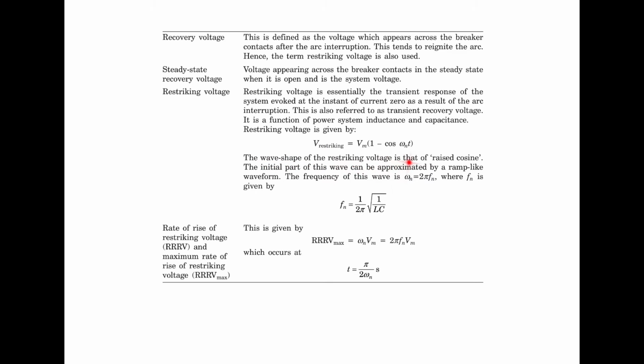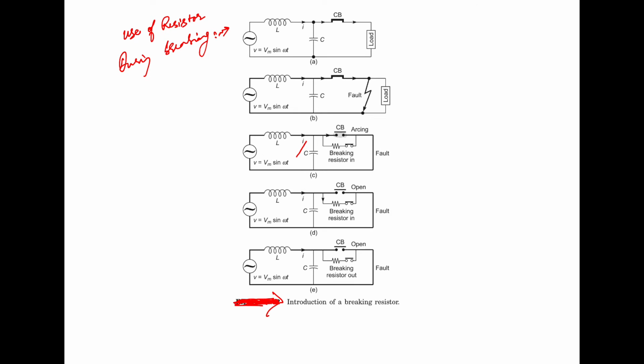The wave shape of restriking voltage is that of a raised cosine. The initial part of this wave can be approximated by a ramp-like waveform, and the frequency of this wave is given by this expression. The rate of rise of restriking voltage is given by this, and the maximum rate of rise of the restriking voltage is this one, which occurs at a time of pi divided by 2 omega n.